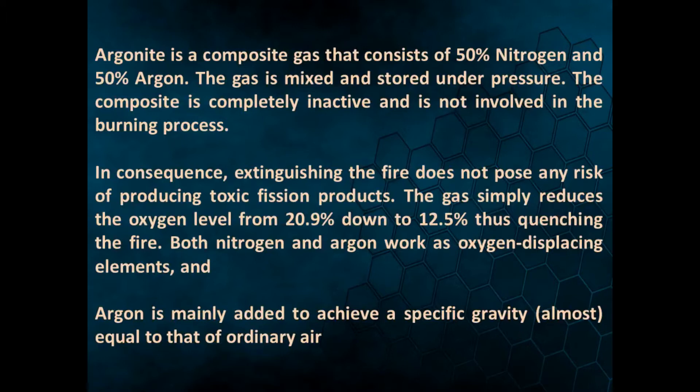The gas simply reduces the oxygen level from 20.9% down to 12.5%, thus quenching the fire. Both nitrogen and argon work as oxygen-displacing elements. Argon is mainly added to achieve a specific gravity almost equal to that of ordinary air.